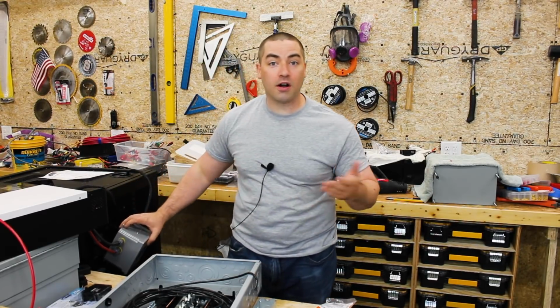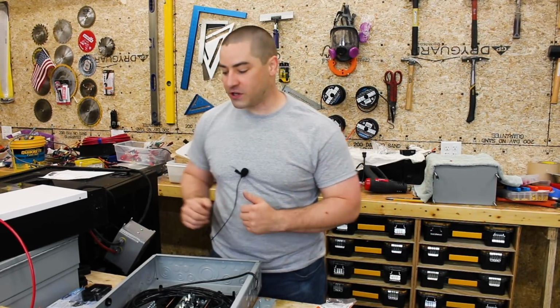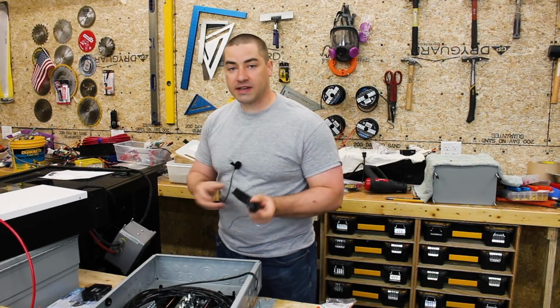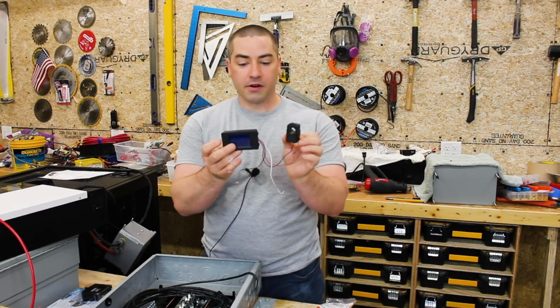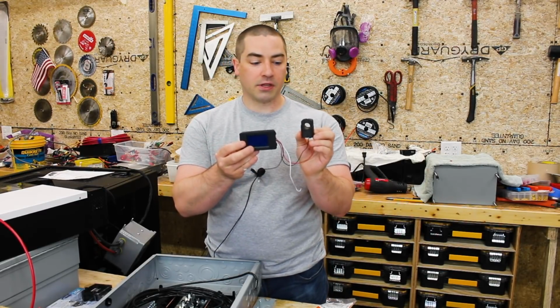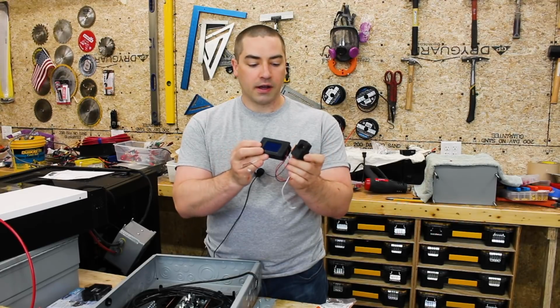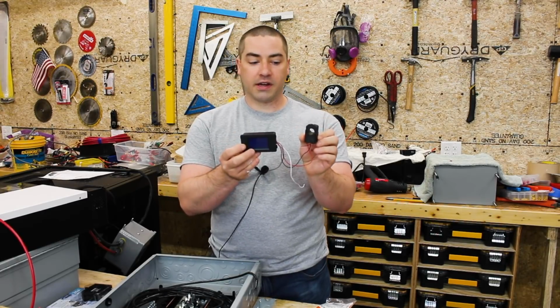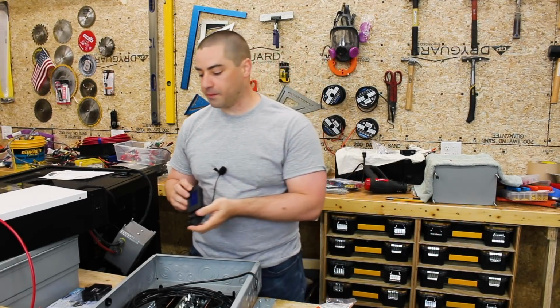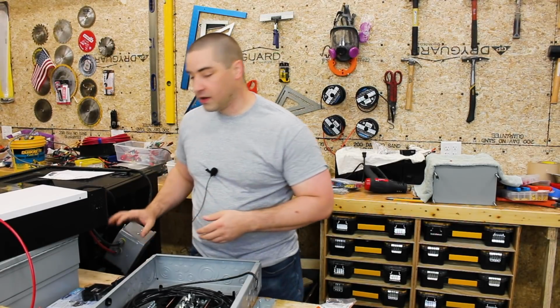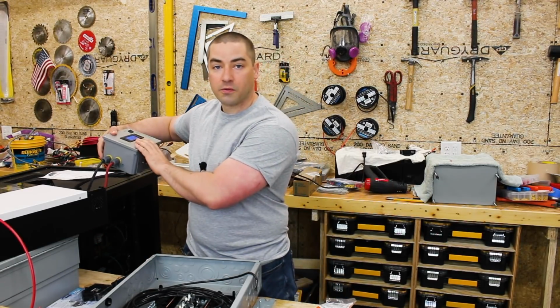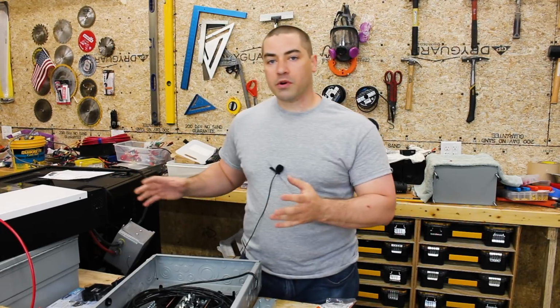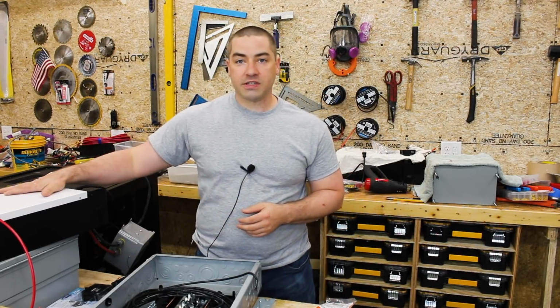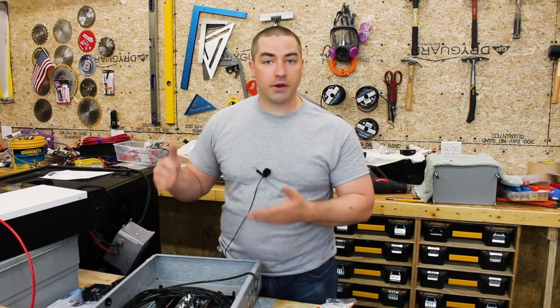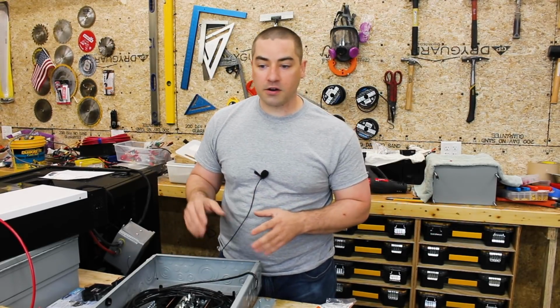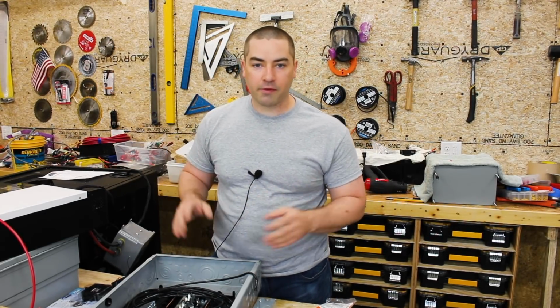So in this video, we're also going to be able to calculate what our efficiency is. Now, for the efficiency test, I also picked up this little watt meter, but this little watt meter is going to be specific for alternating current, which is why we have a little CT clamp, instead of, in this case, for the DC side, we're using a shunt. But we're going to be able to get roughly what our efficiency is. We'll check that at a few different points depending on what our loads are, so we kind of get a rough map of what we're doing.